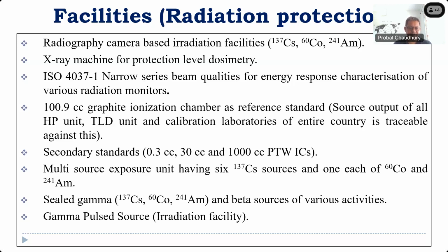Then we have secondary standards, which are 0.3 cc, 30 cc and 1000 cc ionization chambers. Then we have one multi-source exposure unit having 6 cesium-137 sources and one each of cobalt-60 and americium-241. We need different radiation sources because of different energies. Cesium-137 has an energy of 662 keV, whereas cobalt-60 has two energies, 1172 and 1332 keV. So these are the different energy ranges, and the activities will also be different to give different dose rates. Then we have sealed gamma and beta source activity measurement, as well as irradiation to calibrate the irradiation facility. We have a gamma pulse source which can produce a high gamma radiation dose in a very short duration.